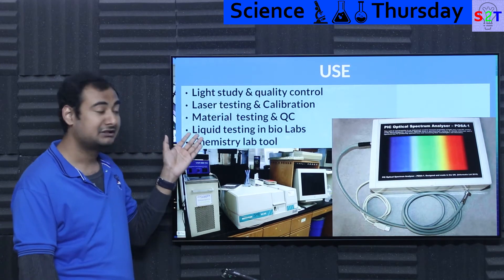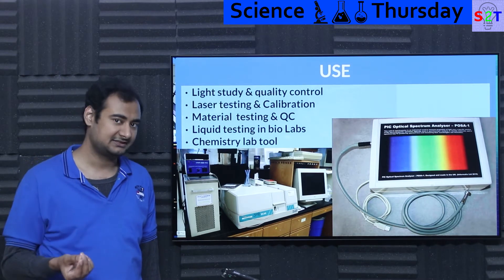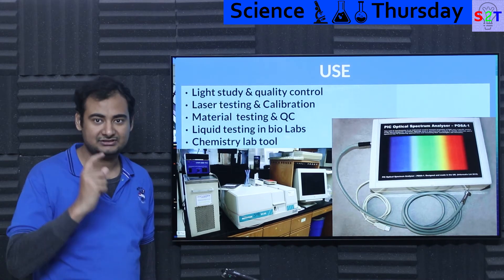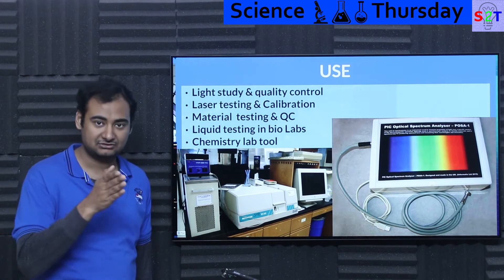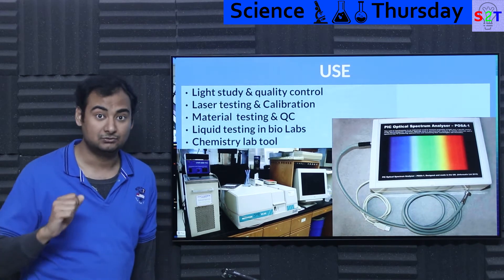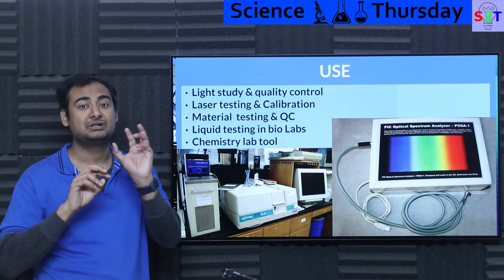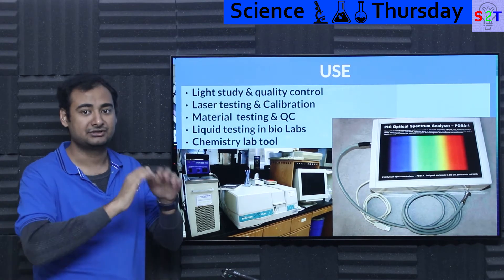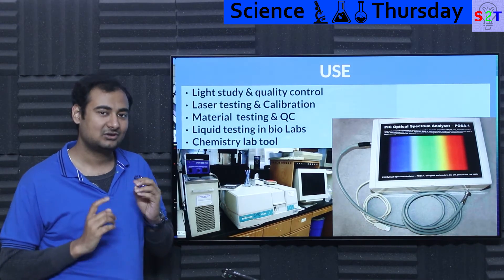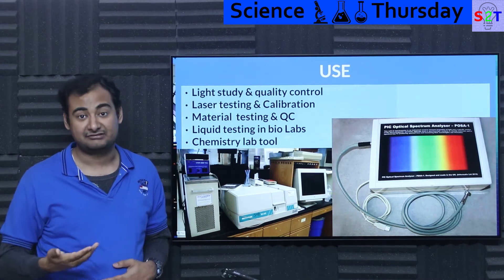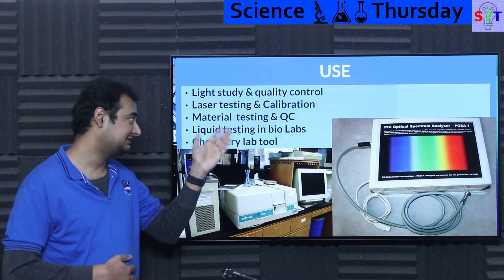Then we come to lasers. Lasers require this instrument because making high-quality lasers is very expensive. People build cheap infrared lasers first — the first CD was based on infrared, then DVDs moved to red, then Blu-ray moved to blue. The consequence is that unless they have a quality infrared filter, your laser output also contains infrared, which is really bad for your eyes. For the laser industry, this instrument is the only way to calibrate and test everything.